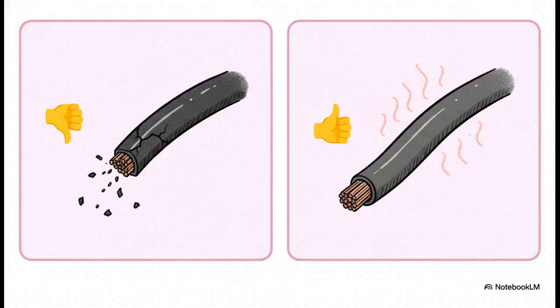The choice of insulation layer is a critical engineering decision. Older cables often use PVC, but it can become brittle over time. Modern cables use a material called XLPE, cross-linked polyethylene, a superior insulator. It can withstand higher temperatures, meaning the cable can safely carry more current, and it has a much longer lifespan.